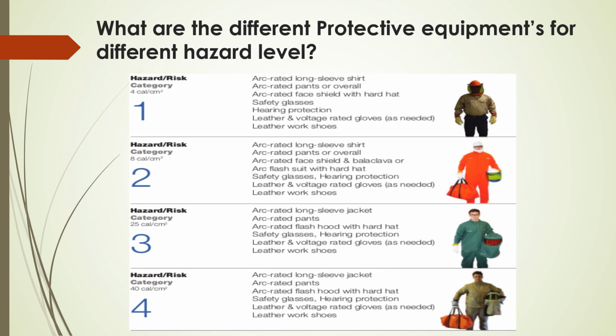and leather work shoes. In arc hazard or risk category 3, basically the incident energy is 25 calorie per centimeter square. Here we use arc rated long sleeve jacket, arc rated pants, arc rated flash hood with hard hat, safety glasses, hearing protection, leather and voltage rated gloves as needed and leather work shoes. Hazard or risk category 4, wherein the incident energy is 40 calorie per centimeter square. So arc rated long sleeve jacket, arc rated pants, arc rated flash hood with hard hat, safety glasses, hearing protection, leather and voltage rated gloves, leather work shoes. So typically these are the four levels of PPEs we use for different incident energy levels.